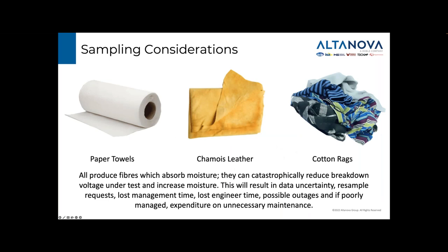Oil sampling and maintenance should not be undertaken with any fibre-producing cloths like the ones shown here. Their use should be prohibited for any activities involving oil handling. The fibres left behind from using these items can have a significant impact on breakdown voltage and moisture results, which can have knock-on implications and cost implications for the asset manager. Wiping down drums with fibre-producing materials is going to leave fibres behind, along with the chance that they will find their way into the oil and disrupt the quality of the sample.